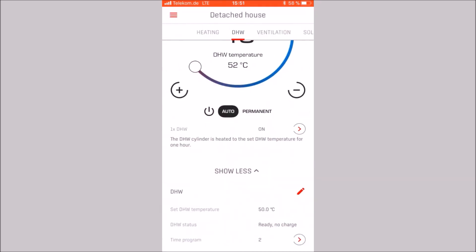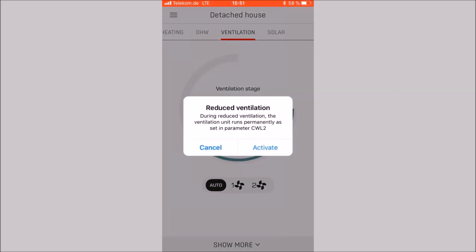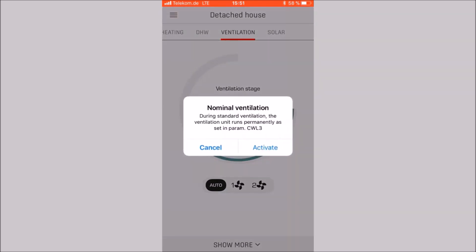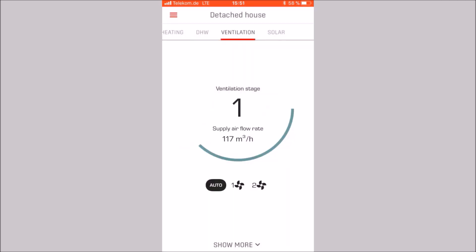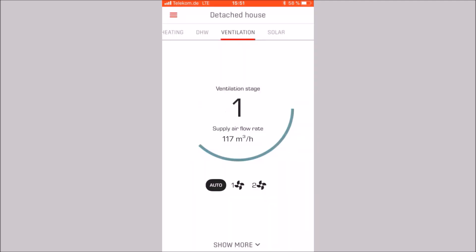Let us go to the category of ventilation. First, you can switch between reduced ventilation and nominal ventilation. The corresponding air quantities can be programmed via CWL parameters. If automatic mode is activated, switching takes place between nominal ventilation within the switching times and reduced ventilation outside the switching times.